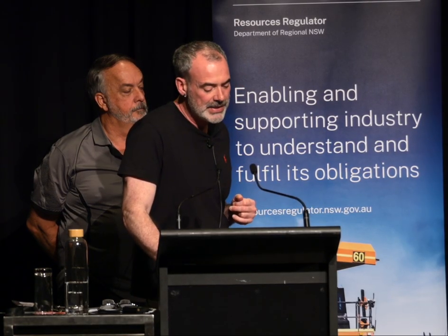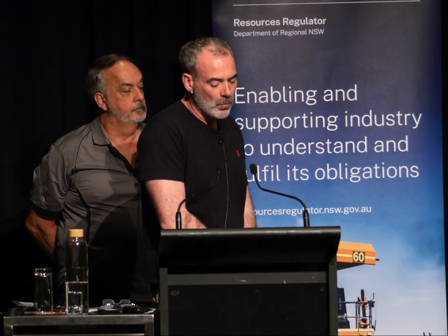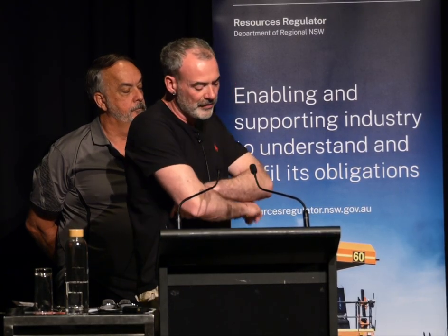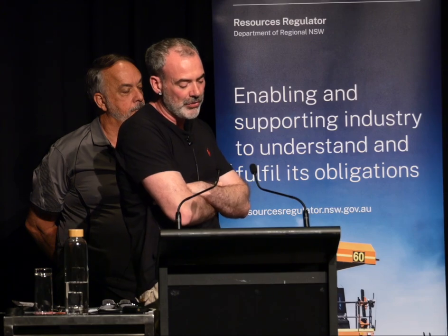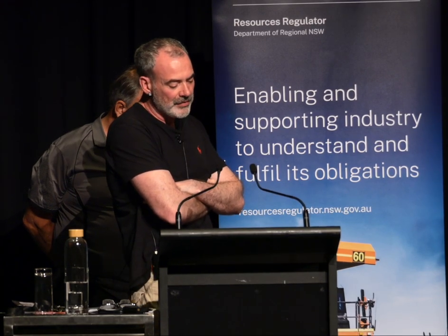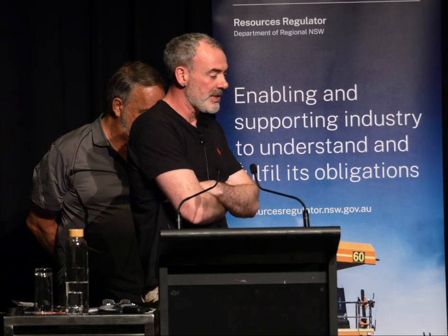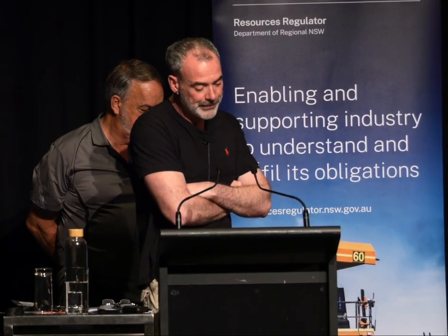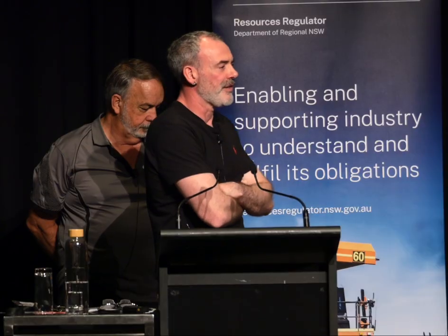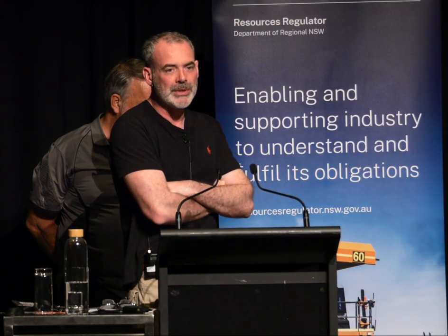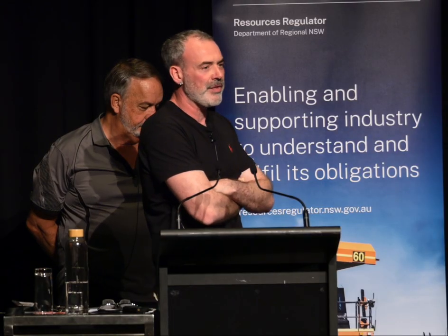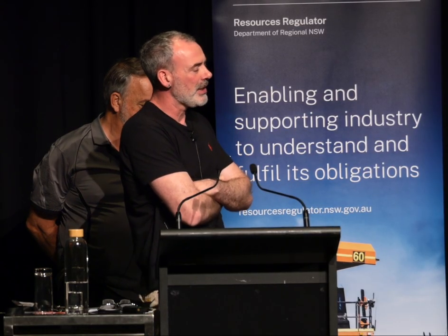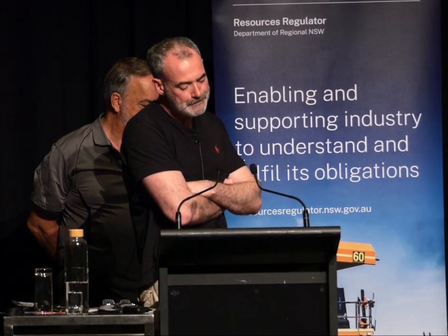After that, if the oxidation inhibitor becomes depleted, oxidation of the fluid will occur, and we would expect to see increases in acidity, viscosity of the fluid, and dielectric dissipation factor, which is what you would monitor with your annual oil analysis program. What we estimate is that even after 10 years of free breathing, the viscosity levels will still be within acceptable levels according to IEEE C57.147. We're definitely not going to see any solidification of the fluid in the main tank. That's not going to happen. Where we'll see solidification of the fluid is on thin layers. It's called thin layer polymerization, and that occurs over 2 weeks at ambient temperature.